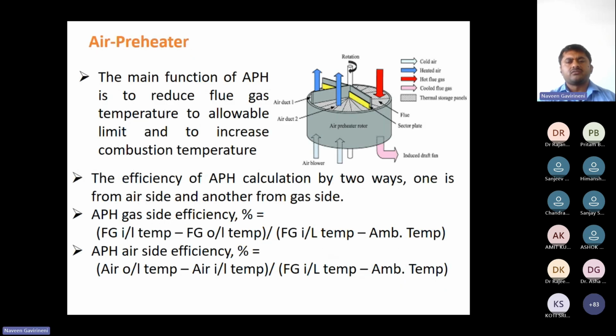So this is the air preheater. As you know, there is a recuperator air preheater. That means on one side we are supplying one stream, so flue gas is going through the APH to the atmosphere. There is a basket arrangement. Once it goes to that basket, the basket picks up heat while rotating.